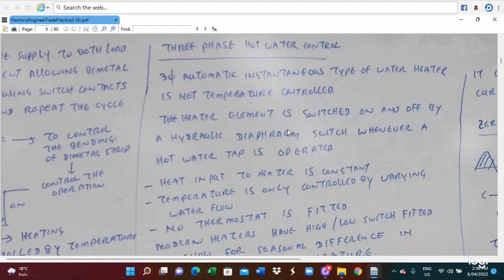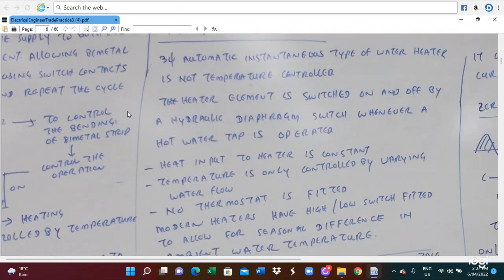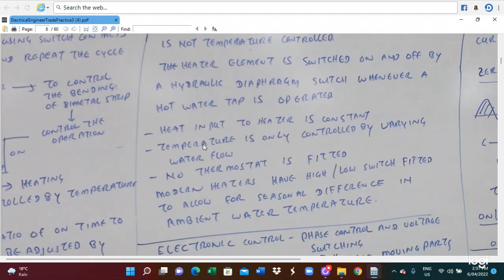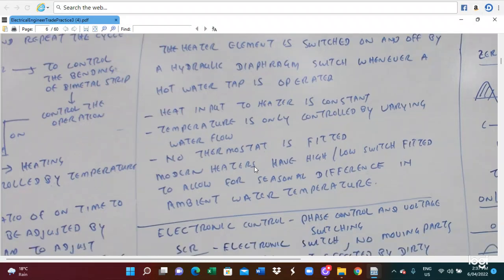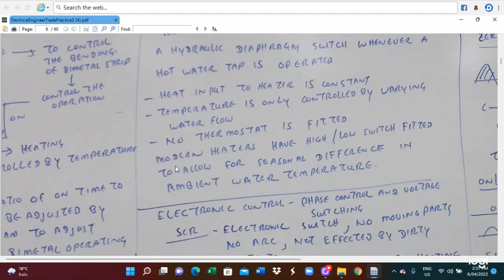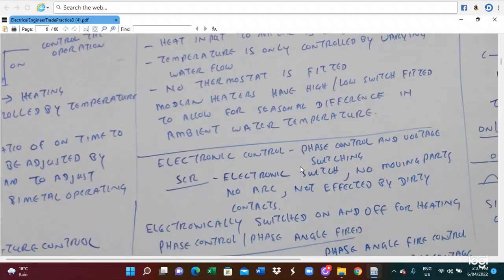The three-phase water control system is also applied. Three-phase automatic instantaneous-style water heater has no temperature control. The heater element is switched on and off by the hydraulic diaphragm switch whenever the hot water tap is operated. Heat input to the heater is constant. The temperature is only controlled by the variance of water flow. No thermostat is fitted. Modern heaters have a high-low switch fitted to allow for the seasonal difference in the ambient water temperature.